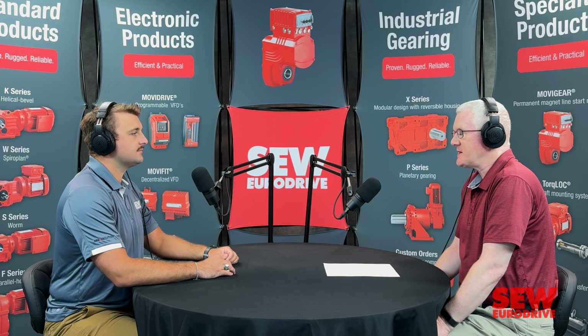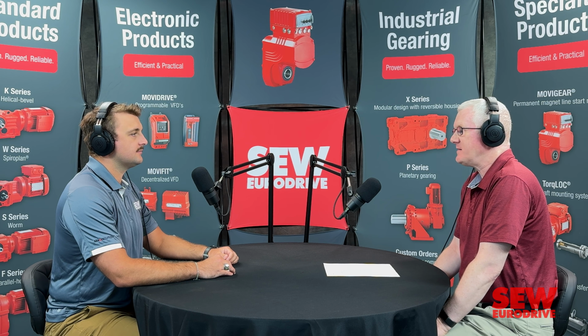Yes, the advantage of fieldbus control is it's extremely powerful. You get enormous flexibility. Now, of course, a lot depends on the capabilities of your VFD on the other side of it, but if you have a powerful VFD, like one of our MOVI-C VFDs, you are essentially sending it commands from your controller, your PLC, over the fieldbus to the VFD, telling it what to do. And you can send whatever speed you want. You can tell it to accelerate or decelerate at different rates. You can do all kinds of specific motion operations.